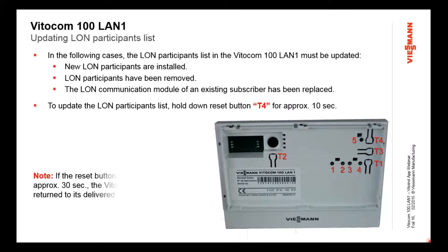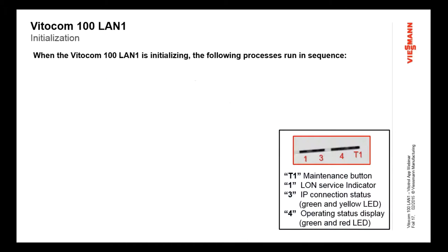Now, if you wanted to reset the whole control back to factory default for some reason, then if you held that T4 button for 30 seconds, it would wipe all of the information that was in the control and send it back to where it was delivered from the factory. So you don't normally want to do that unless you want to reuse a device for somewhere else or something like that. But just be aware that if you hold it 10 seconds, it does a participant check, and if you hold it for 30 seconds, it resets the control. Okay.